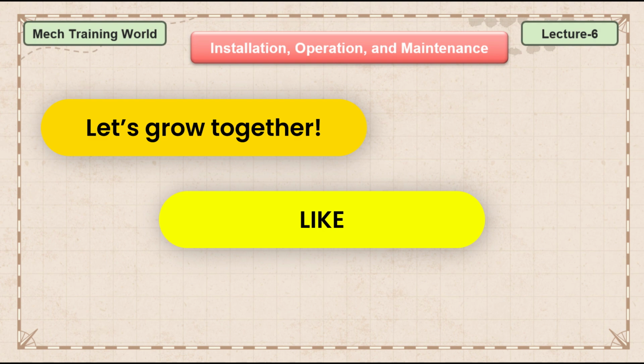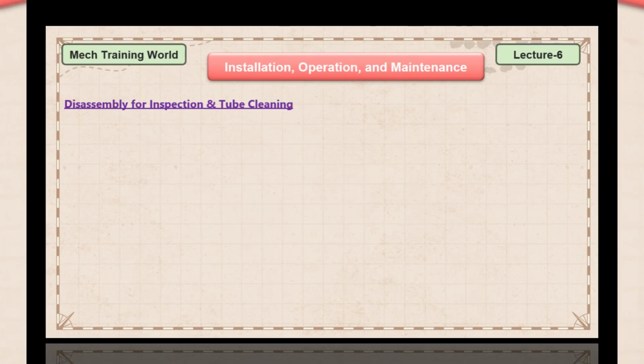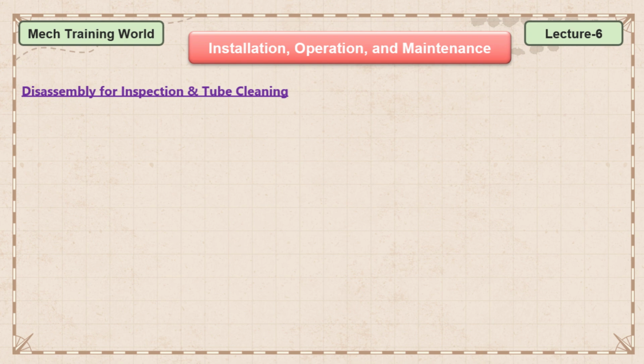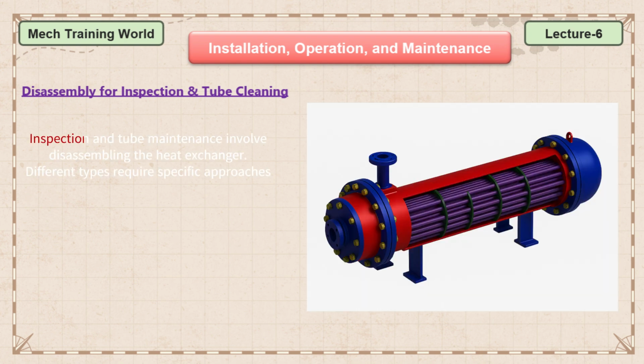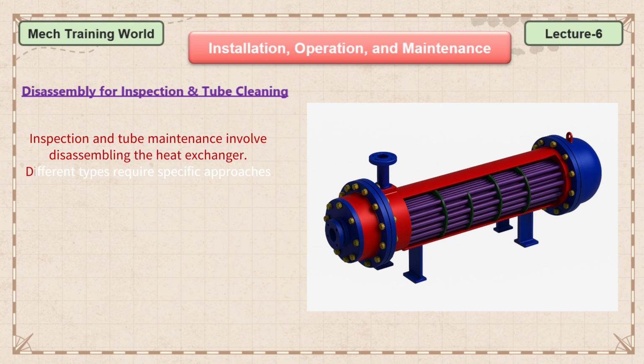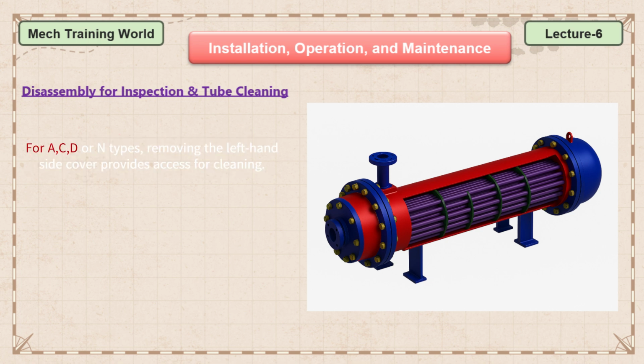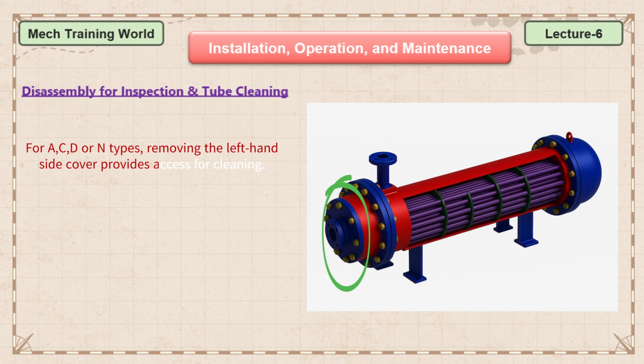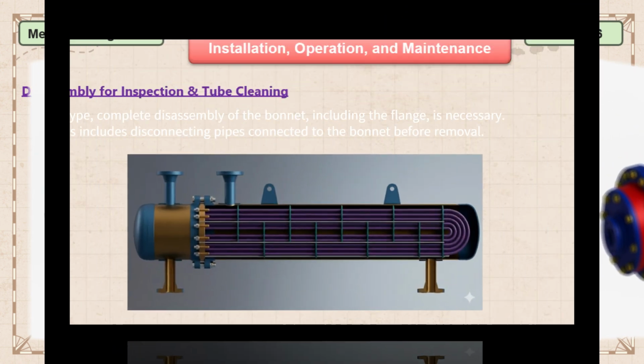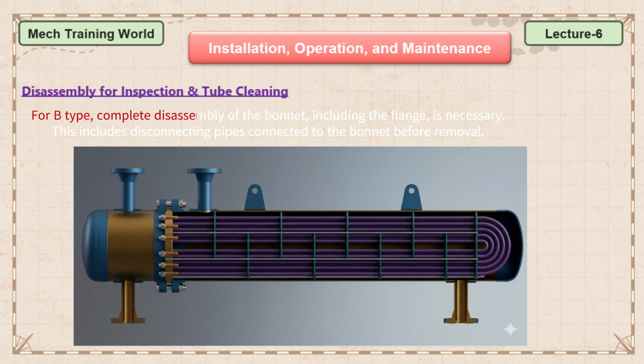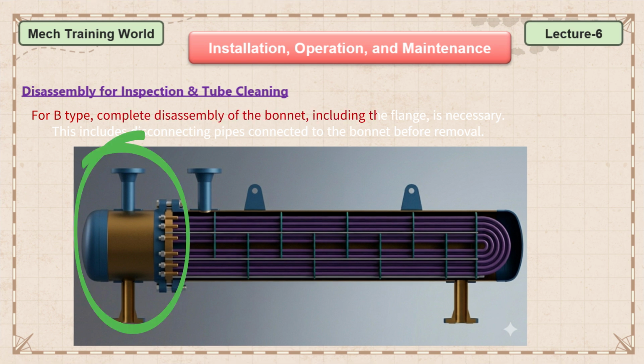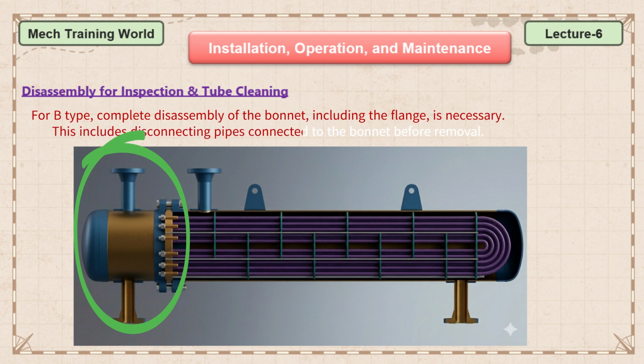Now let's talk about disassembly for inspection and cleaning of tubes. Inspection and tube maintenance involve disassembling the heat exchanger. Different types require specific approaches. For A, C, D, or N types, removing the left-hand side cover provides access for cleaning. For B type, complete disassembly of the bonnet, including the flange, is necessary. This includes disconnecting pipes connected to the bonnet before removal.